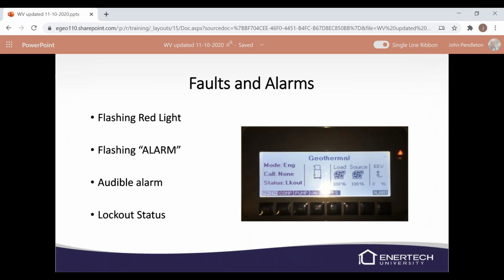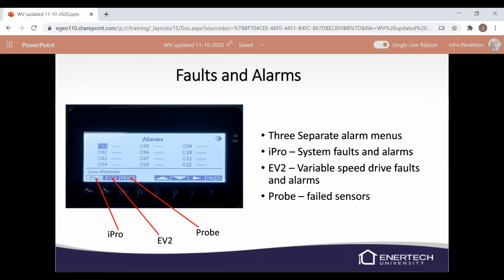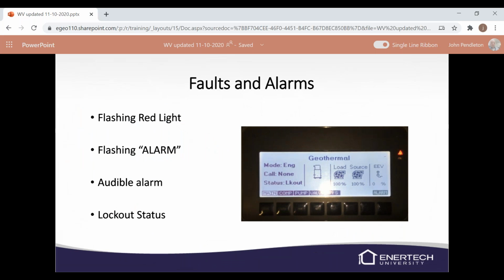Faults and alarms will show a little flashing triangle in the upper right corner on the HMI, and then the alarm button in the lower right corner will flash as well. There will be an audible alarm, a little beeping noise. It's not super loud, so if they're on the other side of the home, they may not hear it. And it will show on the status as lockout.